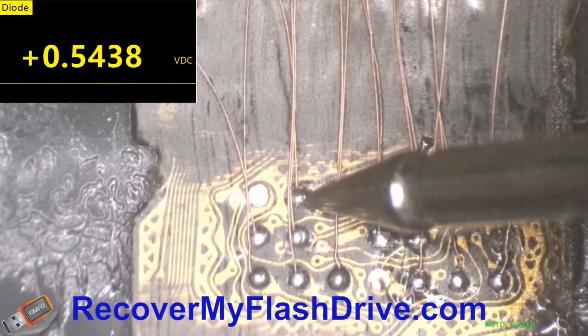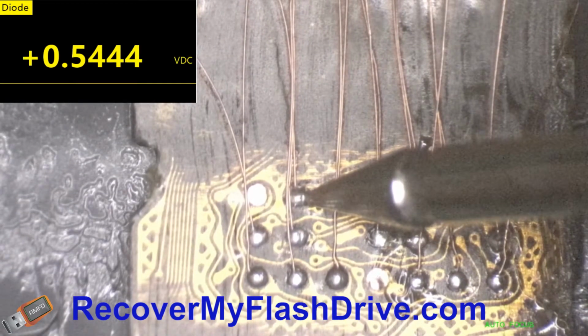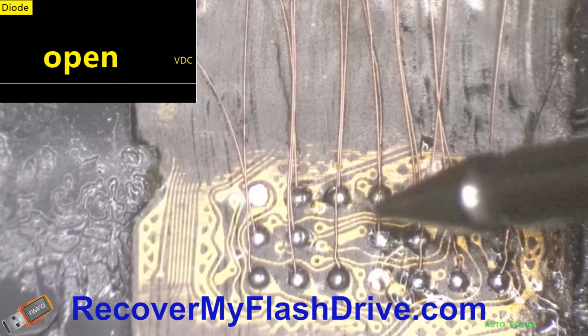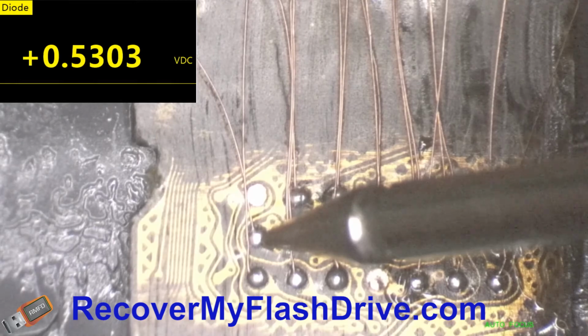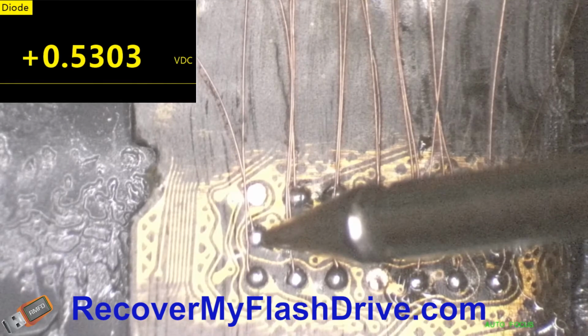In this case, read enable is 0.54, most likely because the signal goes through the control logic and not the data logic. Read busy is 0.53, but it typically has a greater difference from the control signals. Using this information can give you a general idea of what pads connect to what signal, and test for shorts or wrong connections.